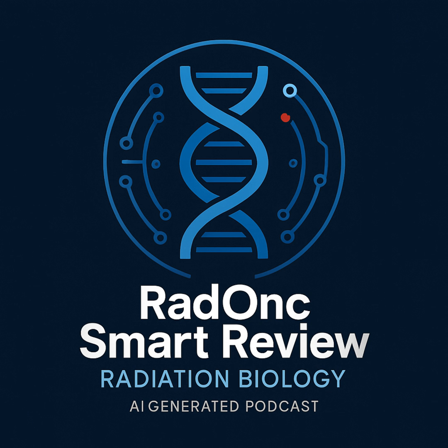Okay. Quick side note on secondary risk, what about neutrons? We sometimes use higher energy beams. Good point. For photon beams with energies above about 10 mega electron volts, and particularly above 15 MeV, you can get what are called photoneutrons produced. Generated in the machine head or even in the patient? Both, yeah. Now, the actual absorbed dose from these neutrons is usually very small. But neutrons are biologically much more damaging per unit dose than photons. They have a high radiation weighting factor, or RBE. So their contribution to the overall secondary cancer risk, while generally considered minor compared to the scattered photon dose, is definitely not zero, especially with those higher energies.